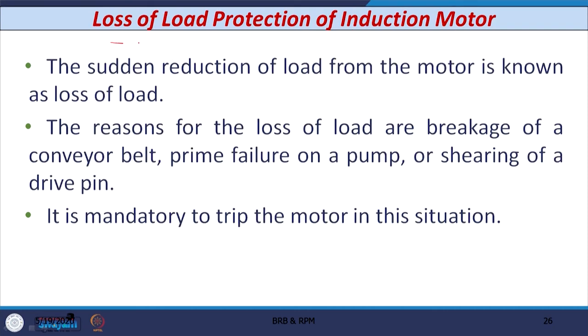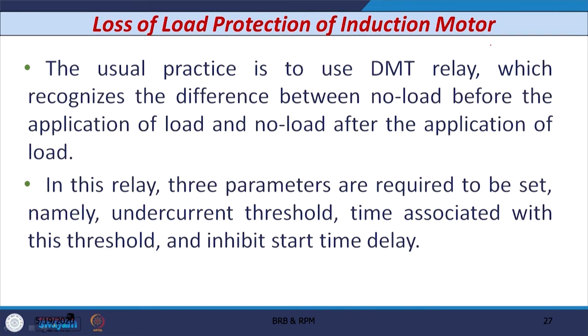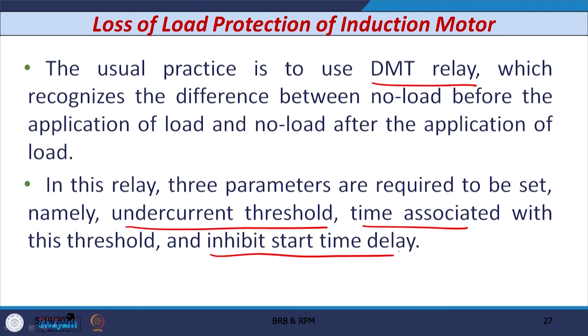The next phenomenon is loss of load protection of the induction motor. The sudden reduction of load from the motor is known as loss of load — maybe because of breakage of a conveyor belt, failure of a pump, or shearing of a drive pin. It is mandatory to trip the motor in this situation. The usual practice is to use a definite minimum time delay relay that recognizes the difference between no load before the application of load and no load after the application of load. Three parameters are required to be set: the undercurrent threshold, the time associated with this threshold, and the inhibit start time delay.